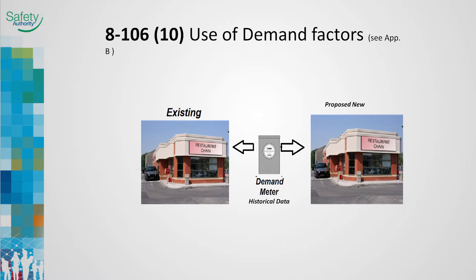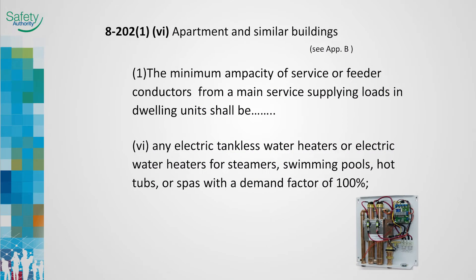Here's an example where Sub Rule 10 might be applied. Rule 8202, Sub Rule 1 is used to determine the minimum capacity of a suite feeder and the panel board size. Item 6 is new and is meant to ensure that the service and feeder calculations account for the on-demand loads required by residential tankless water heaters and similar equipment when supplied by the suite feeder in apartments, townhomes and condominiums. Previous codes provided a generous demand factor which is not suitable for these types of loads.